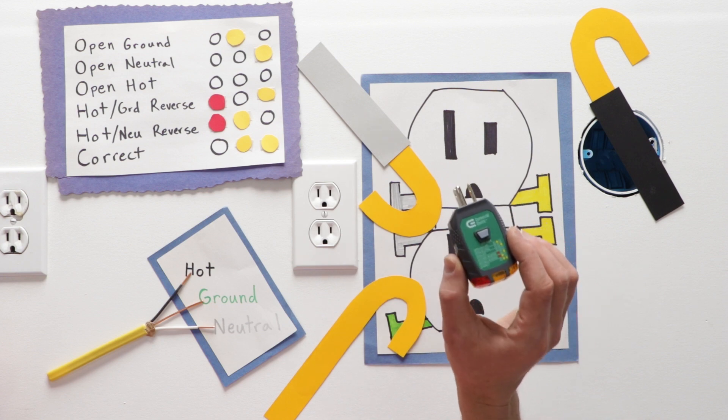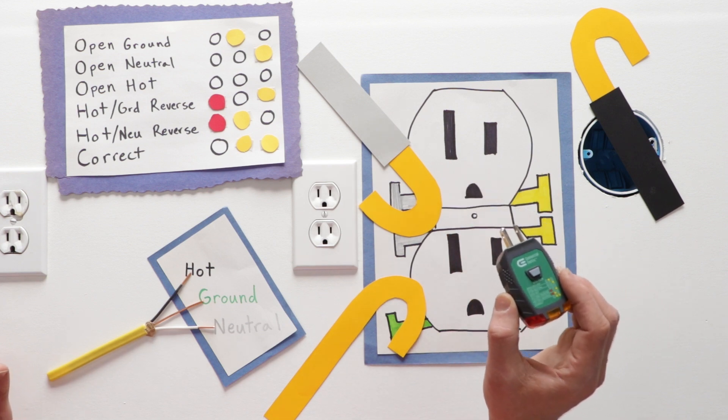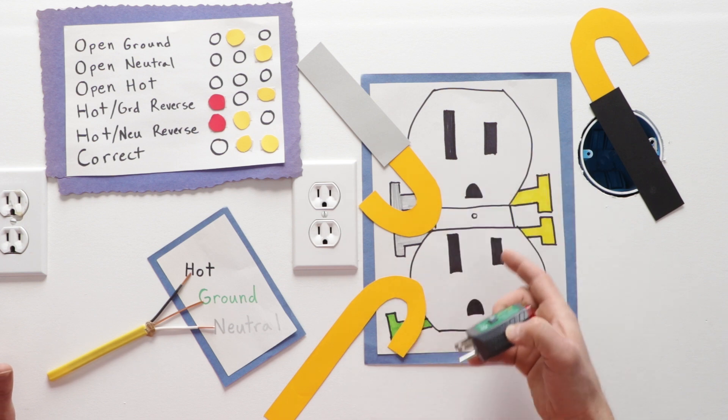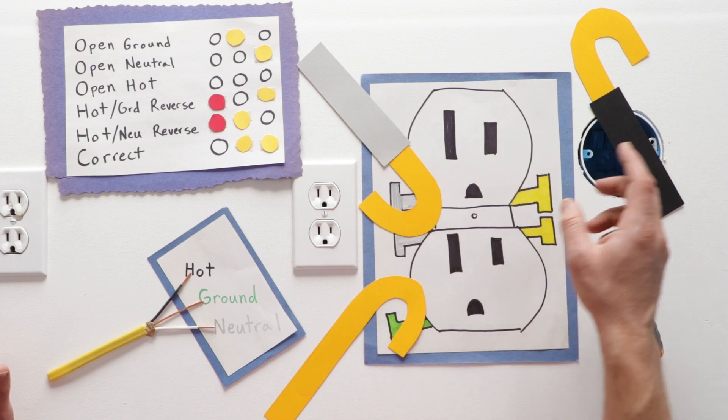But using a receptacle tester is not adequate enough to identify whether or not there is power coming into the box behind the receptacle. Just note, there's no power coming out of the receptacle.